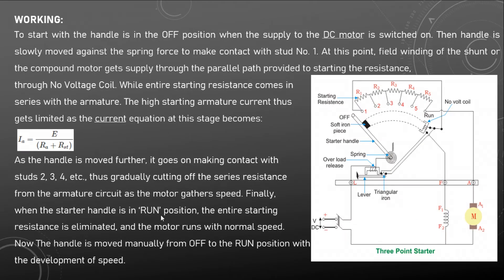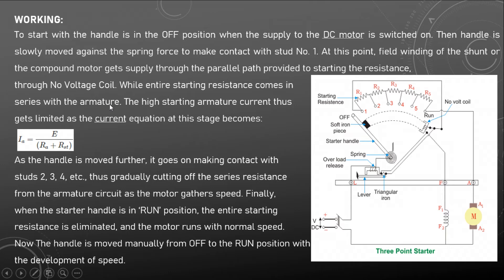Now for the working of the three-point starter: initially the handle is in the off position when supply is switched on. The handle is slowly moved against the spring force to make contact with stud number one. At this point, the field winding of the shunt or compound motor gets supplied through the parallel path provided through the starting resistance and through the no voltage coil.